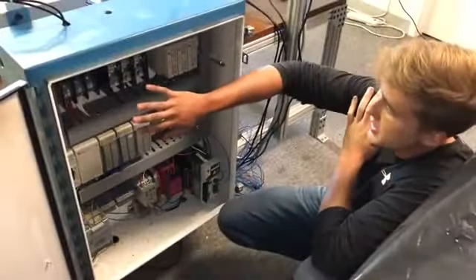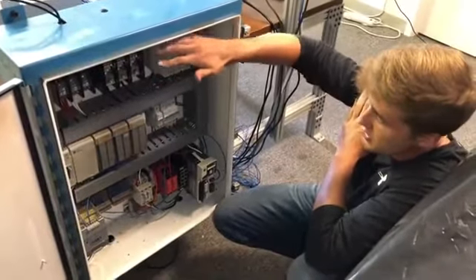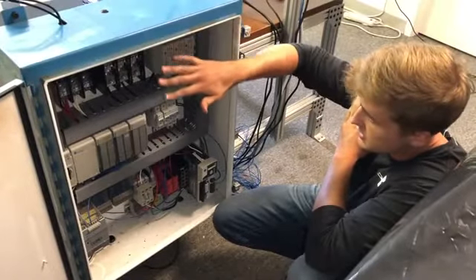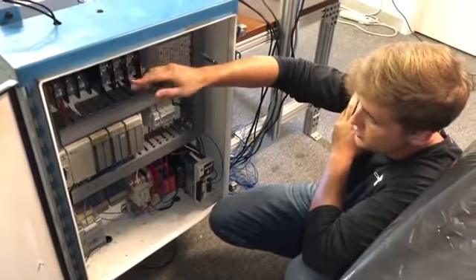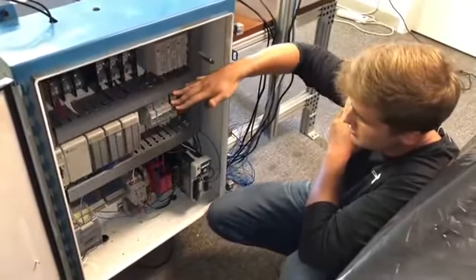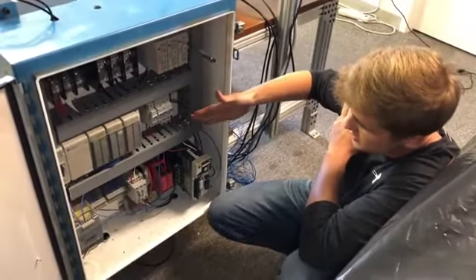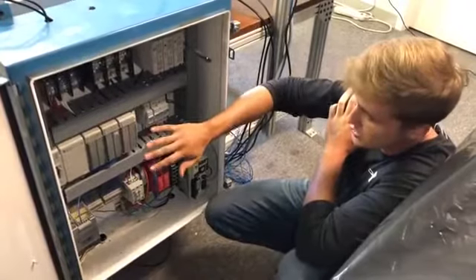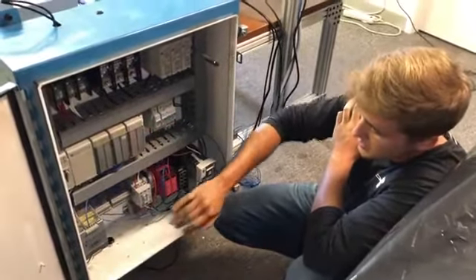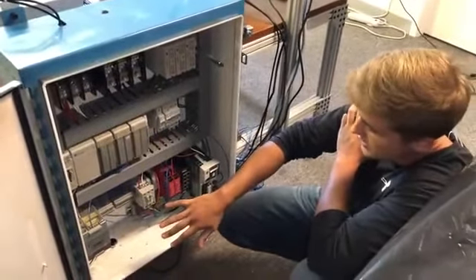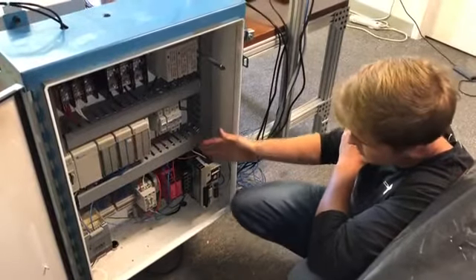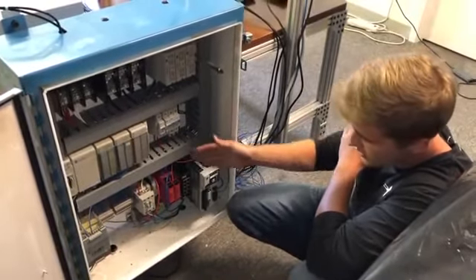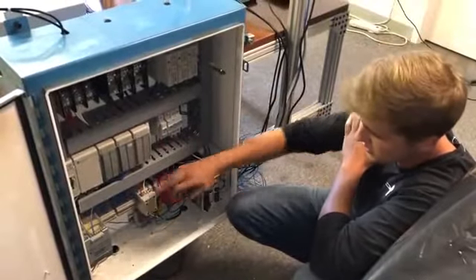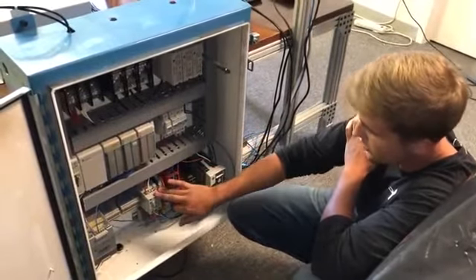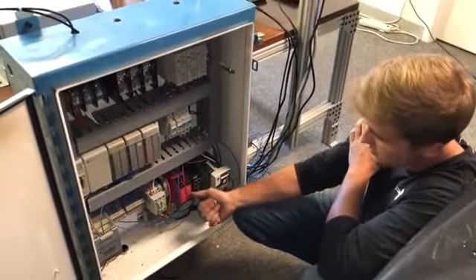So as I mentioned before, we have our main fusing and our two separate power distribution blocks. From the transformer, we're going to have our 120. That's going to lead both to our secondary circuit breakers. It's going to lead to our PLC power supply, our main 24 volt power supply, and externally we're going to have a servo drive running off 120. Our vacuum pump, where here's our motor starter, is going to be running off of 120, and one separate safety relay is also going to be running off of 120.